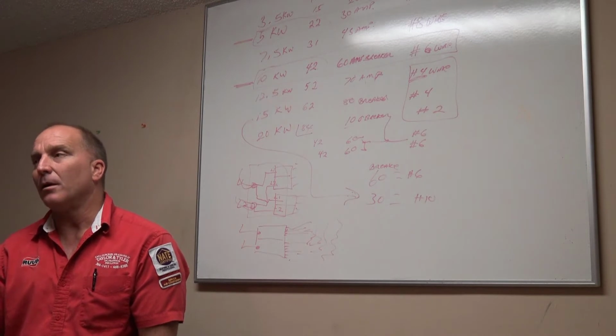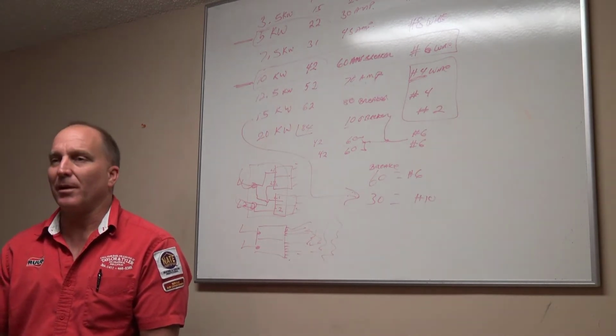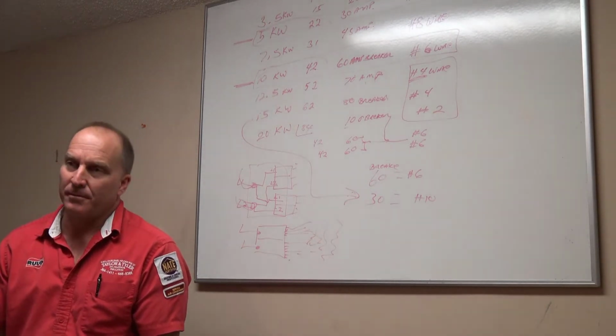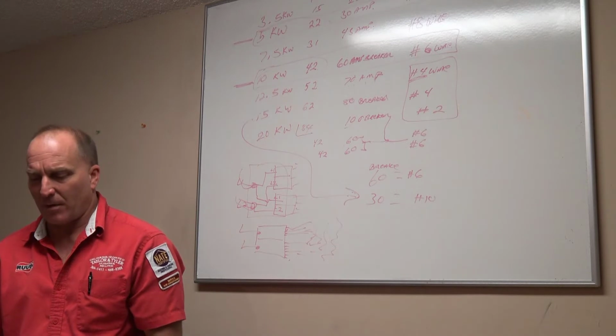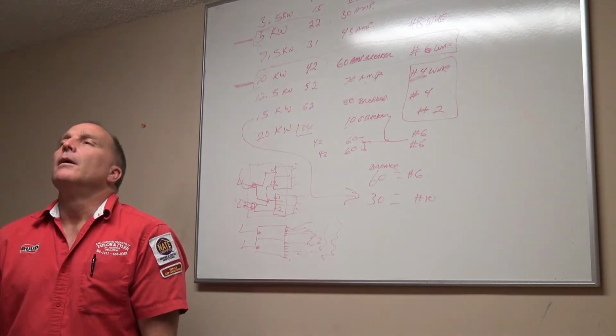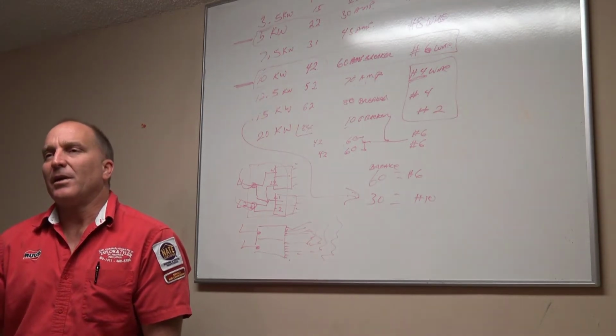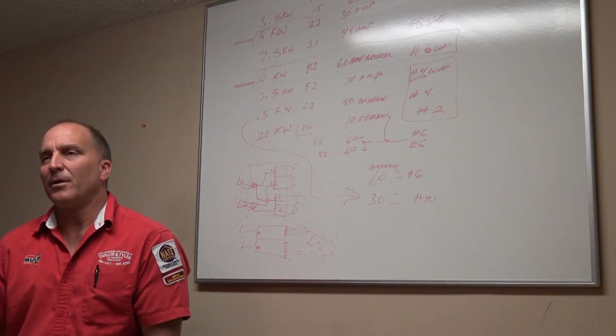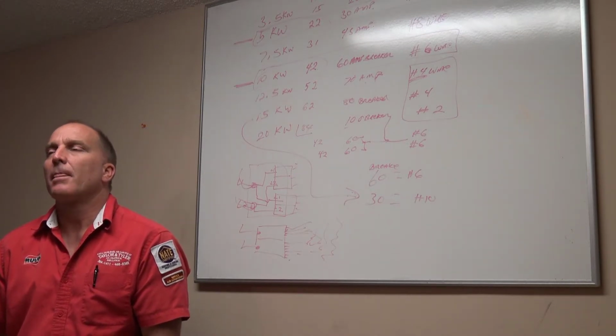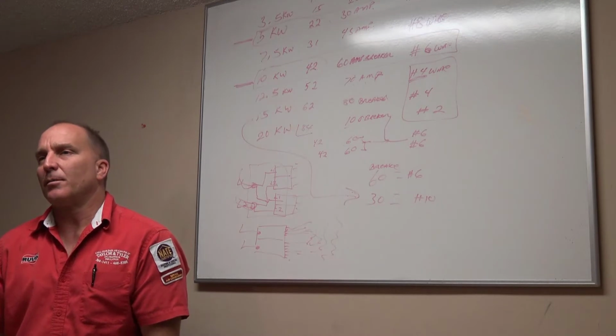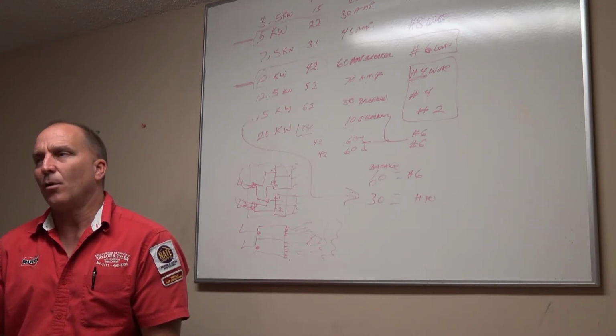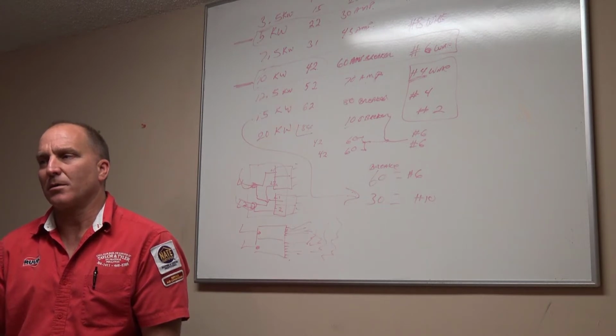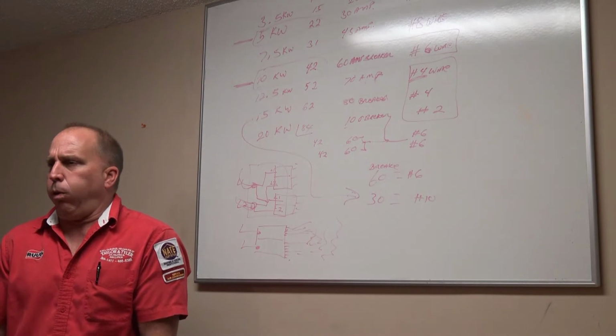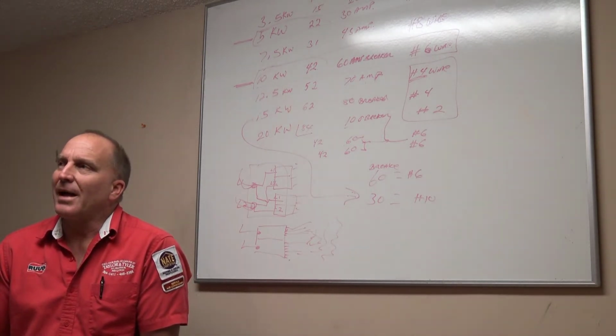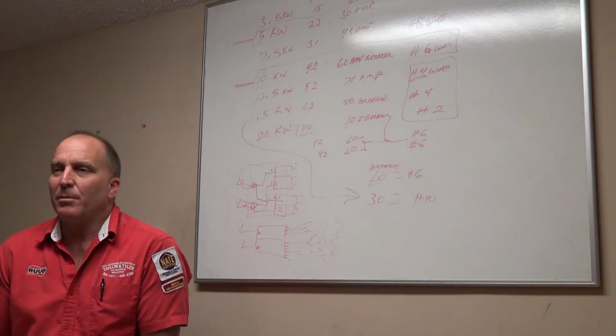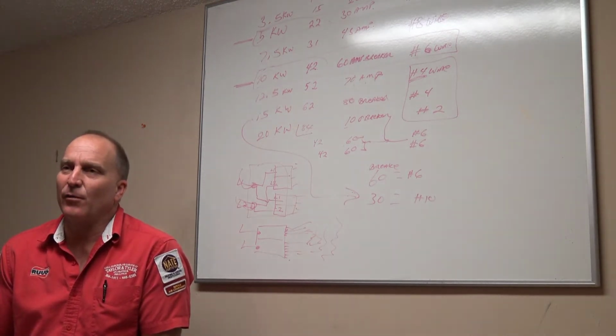On your circuit board, your black wire, high speed, will normally, not all the time, normally go to your cool, depending upon the tonnage of that system and the model number as we have described in other videos. Your low speed will probably be your heater, depending upon the BTU capacity of the heater, how big your house is, how leaky your house is, the whole 9 yards. Your M1, M2 on your circuit board will probably be your yellow and your blue wire, because those are taps. Your SEC, secondary, is going to be your blue and yellow wire from your secondary from your transformer onto your circuit board.